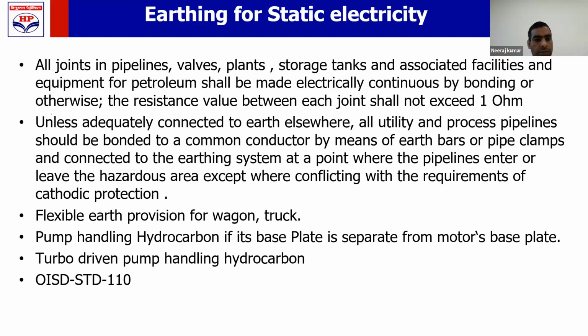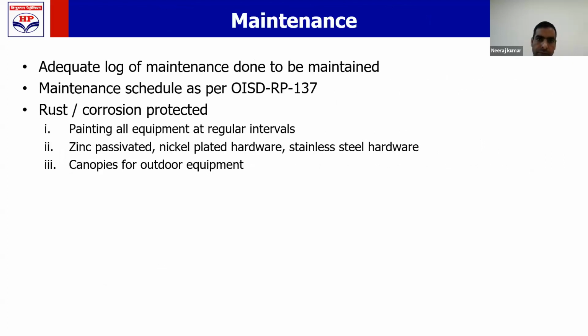A flexible earth provision for tanks and wagons will be provided. If a pump is driven by a turbine, not by a motor, and it is carrying hydrocarbon, then that pump still needs to be earthed. OISD standard 110 is for static electricity, which will discuss these things in detail. In short, I have discussed. For maintenance, OISD RP 137 should be followed.